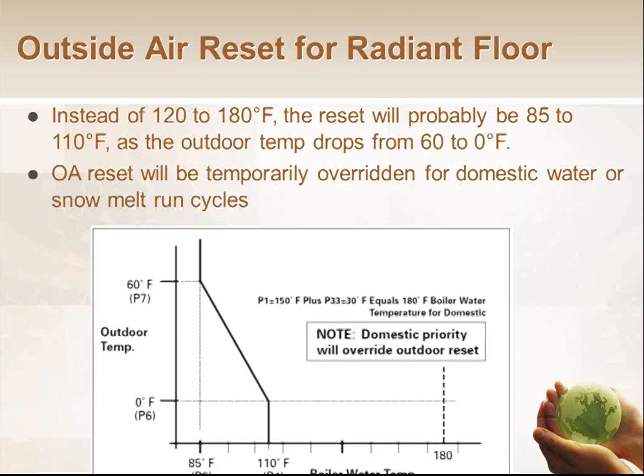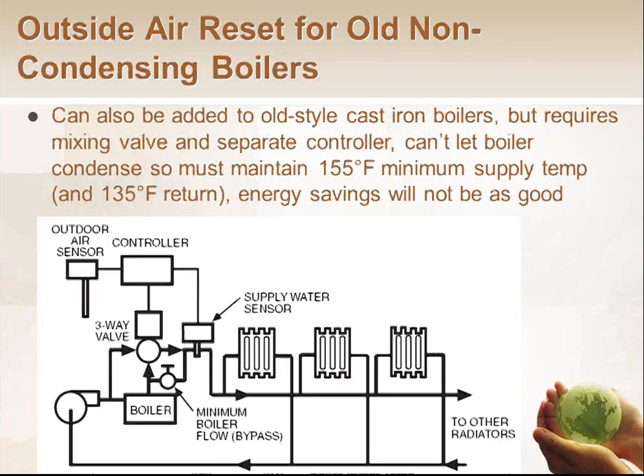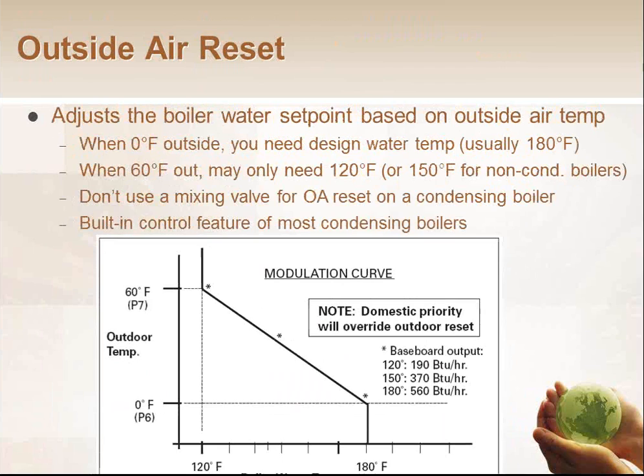With a cast iron radiator or baseboard or air handler job, I'm only going to be in a condensing mode some of the time. But the more time I can get there, the better, and the outside air reset schedule helps me get there. You can put outside air reset controls on non-condensing boilers. It does make some sense to save energy, right? Because like we said, the cooler the water we provide, the more energy we save. However, I can't get really aggressive with the schedule because I can't let that return water drop below, say, 140. So I can really only do half of this outside air reset curve, right? I can do this part of the reset down here, but I can't do the other half of the curve, so I don't get quite as much energy savings.